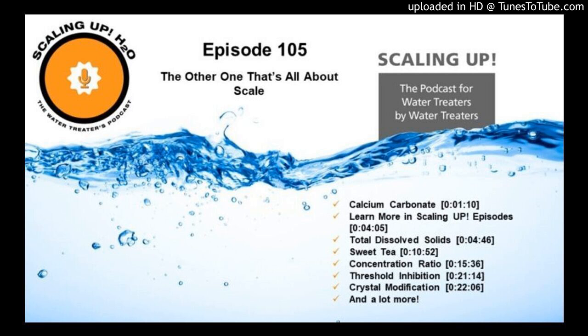However, when we are looking at the multiplier that we use in figuring out if water is either precipitating or dissolving calcium carbonate, conductivity, or in this case, total dissolved solids, is such a small factor, we're not going to see very much difference if we interchange those numbers. So that being said, it is perfectly fine to use conductivity as a substitution for your total dissolved solids numbers when you're using these scaling indices.